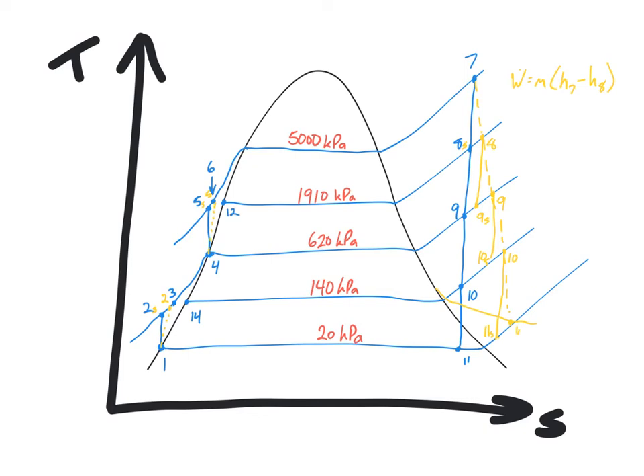From state twelve we go through a steam trap, dropping down to state thirteen. State thirteen is at the same pressure as states fourteen and ten. The trap is a constant-enthalpy process — you can't directly see that on a TS diagram — but as pressure drops, some steam is generated, so state thirteen has some quality at that lower pressure. Similarly, state fourteen traps down to state fifteen at the lowest pressure, going back to the condenser.